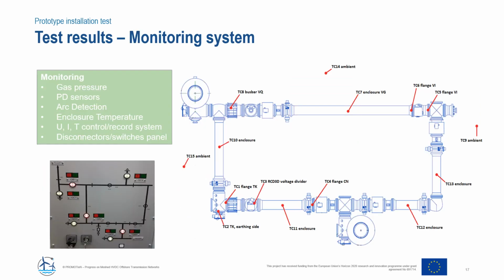Before I go into the test results, I would like to show you the monitoring system that has been used. Of course, many monitoring systems have been on board this HVDC GIS. For example, gas pressure check, partial discharge sensors put onto the device, and arc detection in case there is some flashover inside of the GIS tank.